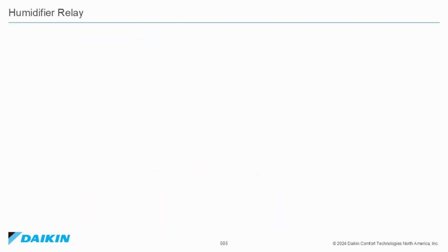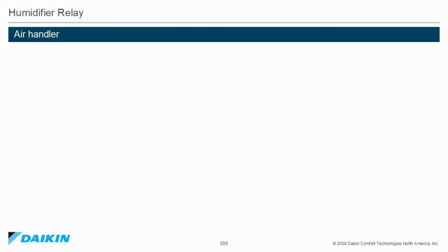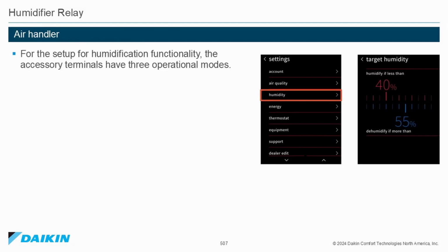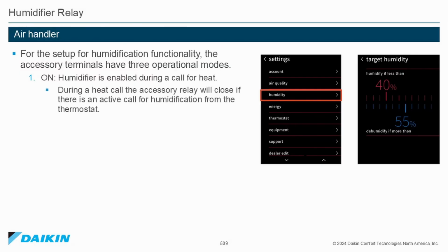Humidifier relay. Air handler. For the setup for a humidification functionality, the accessory terminals have 3 operational modes. 1. On. Humidifier is enabled during a call for heat. During a call for heat, the accessory relay will close if there is an active call for humidification from the thermostat. 2. Off. Humidifier remains off. Relay is open.